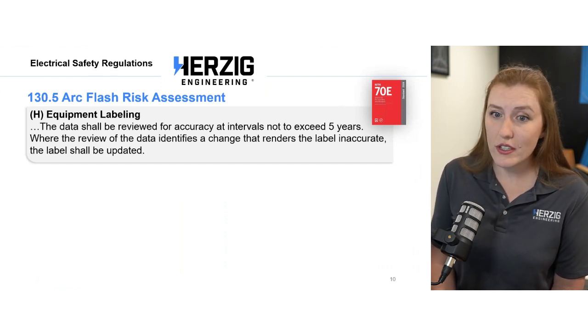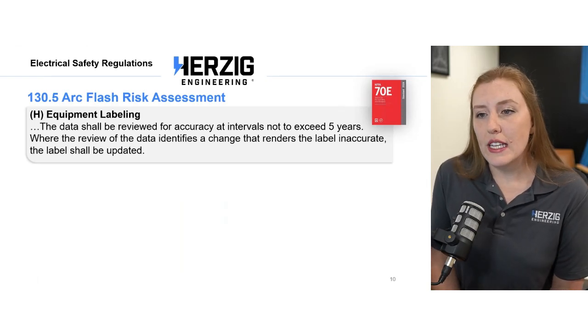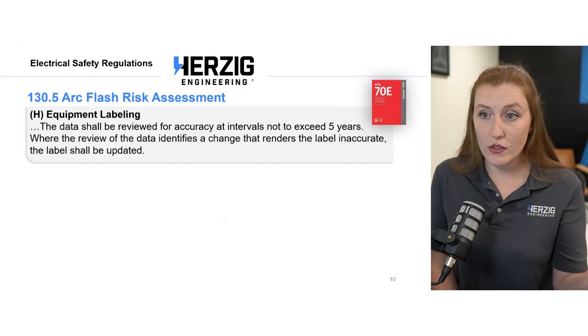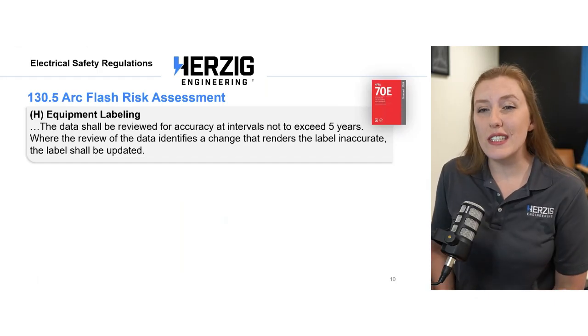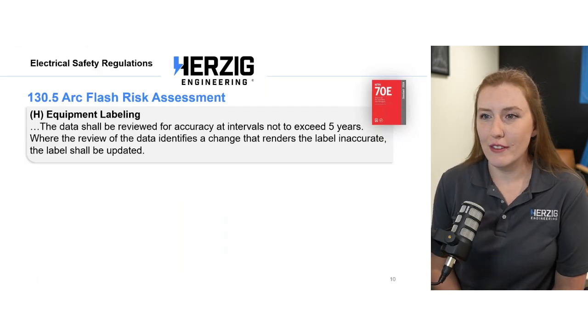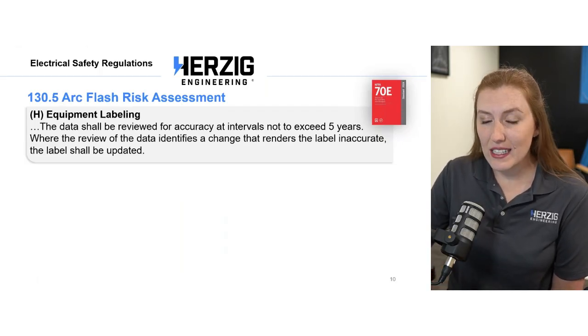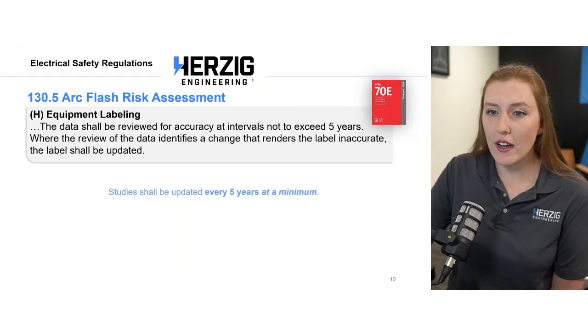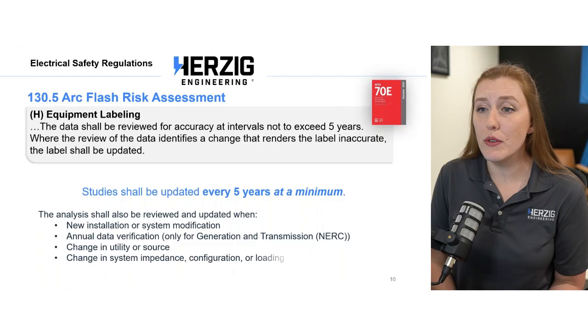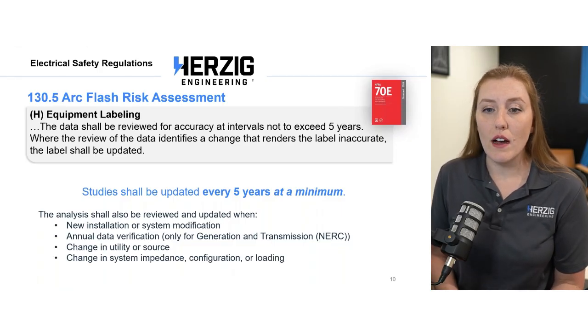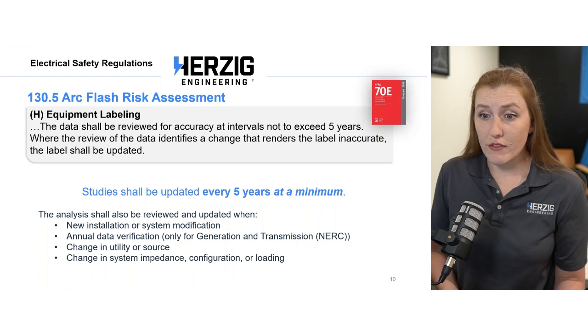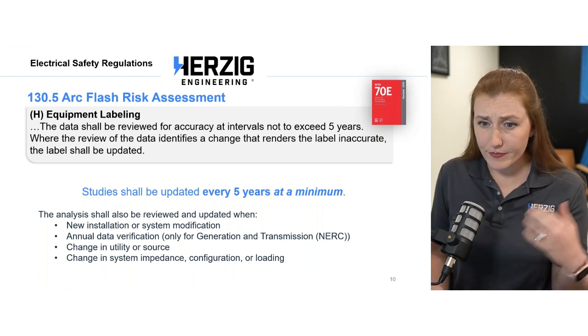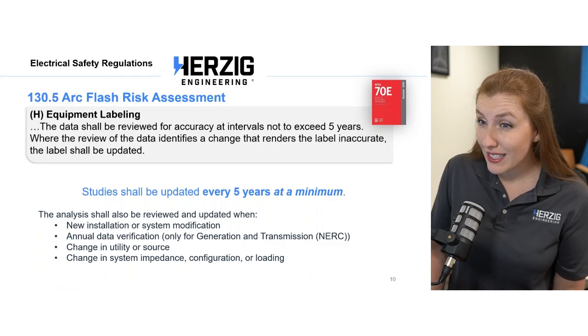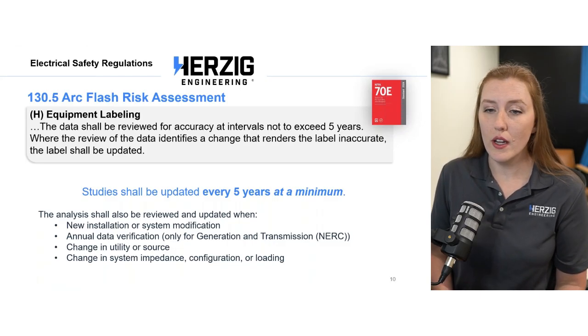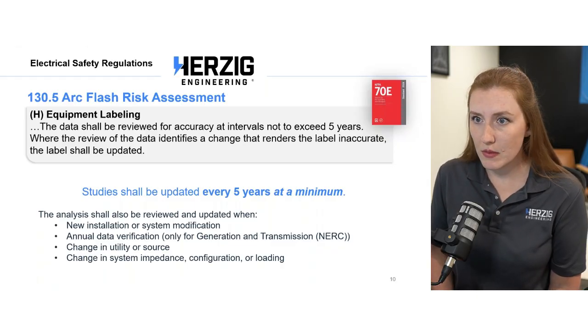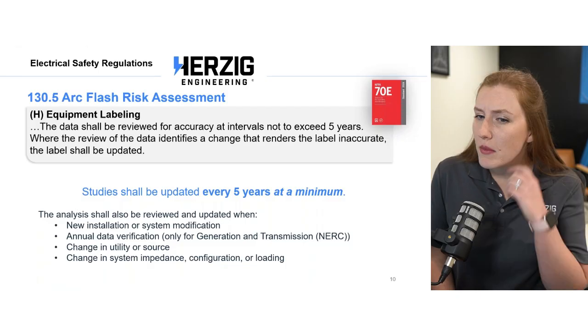The calculations have changed. So the data does need to be reviewed for accuracy at intervals not to exceed 5 years. Those labels, the study itself, make sure that it actually still applies at a minimum every 5 years. Because, again, it's based on a specified set of conditions whenever you calculate that hazard. So anytime you have new installation or system modification, or you have data verification needed for generation and transmission stuff, that's going to impact the study. If you have a change in utility source, different utility transformer, or they've done some work on the overhead lines, they've done some different stuff, different configurations, that could impact some things.